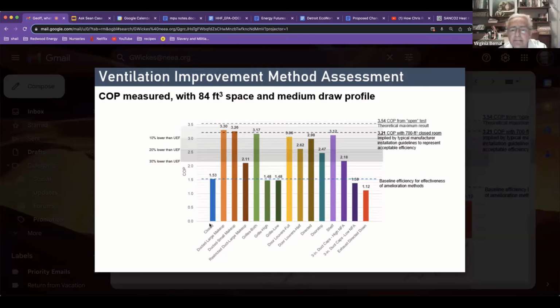This 3.3 figure is for ducted setups with a large makeup air, so you have to put a bunch of money into big duct work to do that right, or ducted with small makeup air. But the problem I've found is that even if the duct work is installed correctly, if it's in any way kinked, the weak fan inside drops your efficiency down from 3 to about 2, all because the duct work wasn't done quite right. So I've found it's safer and guaranteed to work right if I just put a louvered door on it instead of bothering with duct work that could go well or not. Fully louvered doors are a very efficient strategy. Thank you. You're welcome.